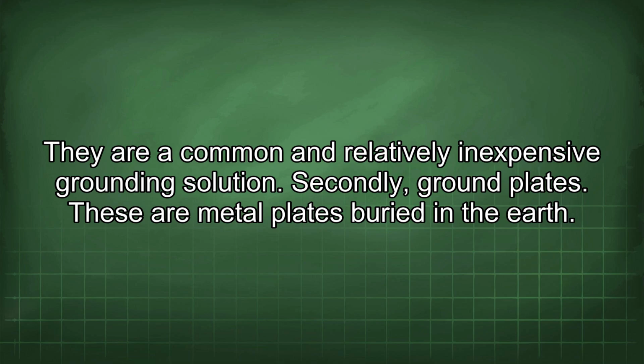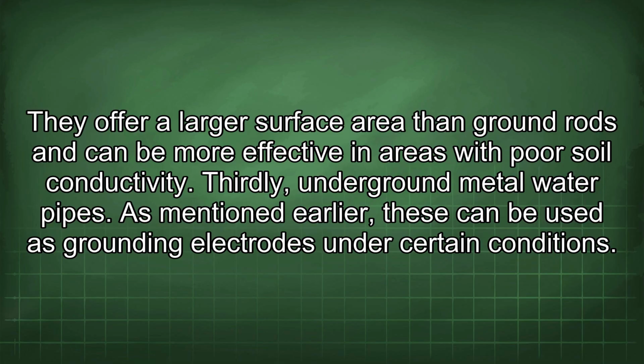These are metal plates buried in the earth. They offer a larger surface area than ground rods and can be more effective in areas with poor soil conductivity. Thirdly, underground metal water pipes. As mentioned earlier, these can be used as grounding electrodes under certain conditions.